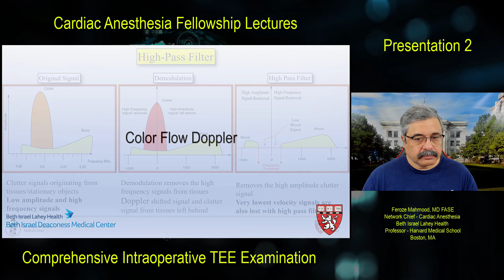So that brings us to color flow Doppler. Now this is a little bit more complicated, and we will get into a little more detail of what a color flow Doppler signal is. First and foremost, a color flow Doppler signal is a pulse wave Doppler signal, because obviously you are locating the flow at a certain specific point in the field of view. As opposed to a pulse wave sample volume at a precise location, we have multiple pulse wave volumes over a region where we put the entire color flow box. And we want to know the Doppler shift or the motion of all those signals either away or towards the transducer.